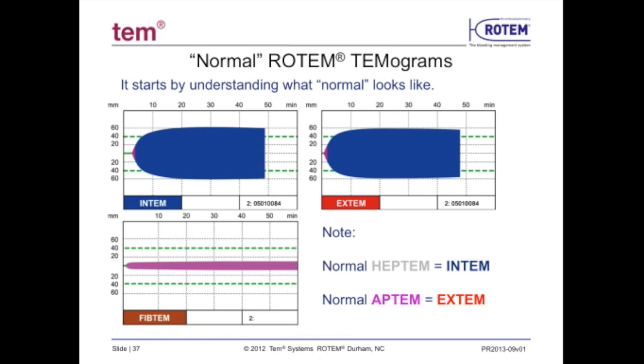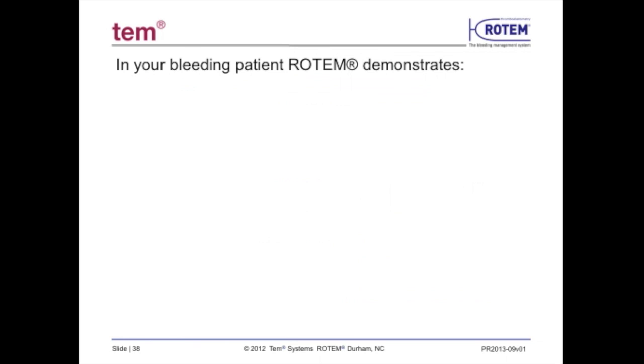A normal Heptem will look like a normal Intem, and a normal Aptem will look like a normal Extem. If these results were demonstrated in a patient with clinically significant bleeding, the cause would likely be of a surgical nature or due to a condition not detectable with Rotem analysis.